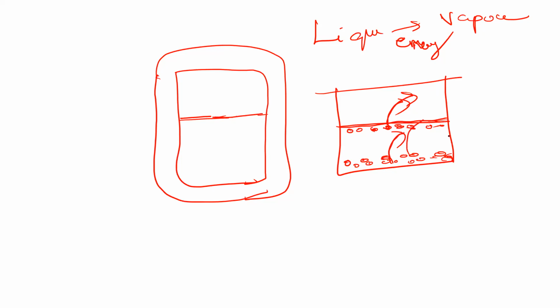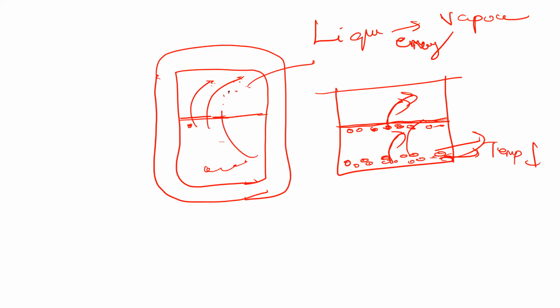So when they lose their energy, what happens to the temperature? Drops. It cools down. That's how this liquid oxygen is able to maintain its own temperature. So when you're using the vapors for hospital purpose, what happens? The top layer gets vaporized, the bottom layer gets cooled down. When you again use, the top layer gets vaporized, the bottom layer gets cooled down more. So this latent heat of vaporization itself keeps the liquid oxygen temperature at minus 150 to minus 170 degrees Celsius. There is no external cooling applied.